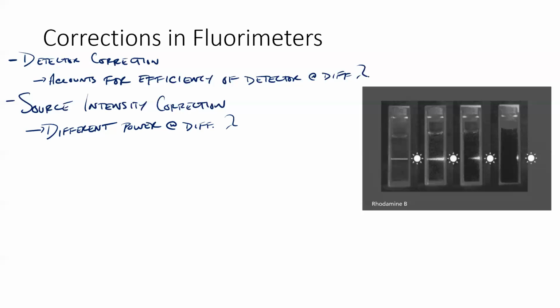In fluorescence, we don't do a background, really, because we assume that the background is zero. Since we're measuring orthogonal, there shouldn't be anything. And so usually, again, the instrument has some calibration already built in for the light source. That, okay, I know this is a xenon bulb, and here's the power curve for it, and so I have to adjust at different wavelengths. So those two are largely taken care of by the instrument, and we don't worry about them too much.